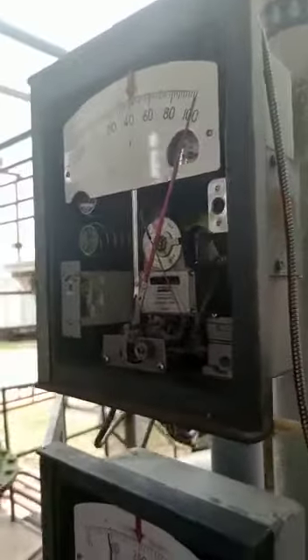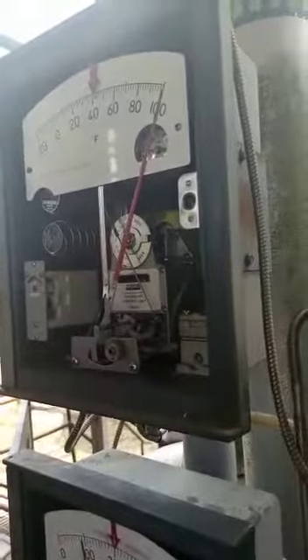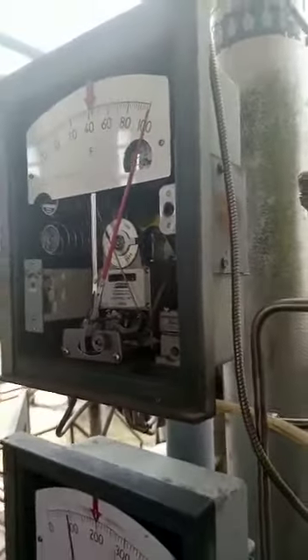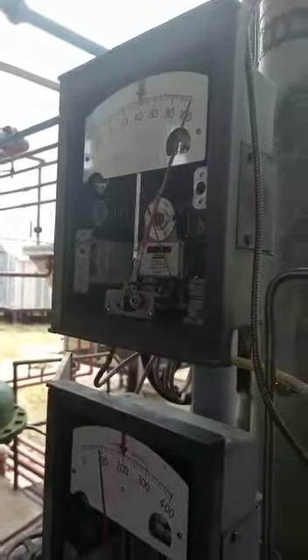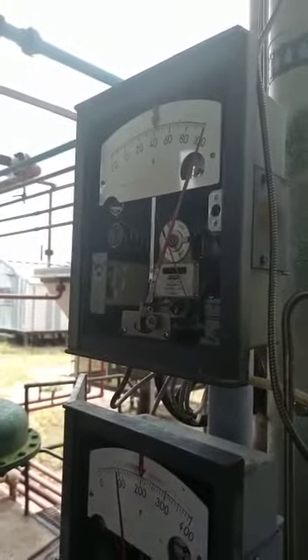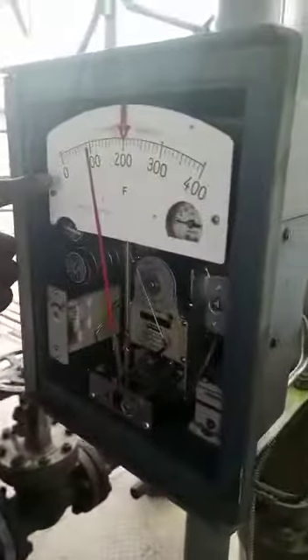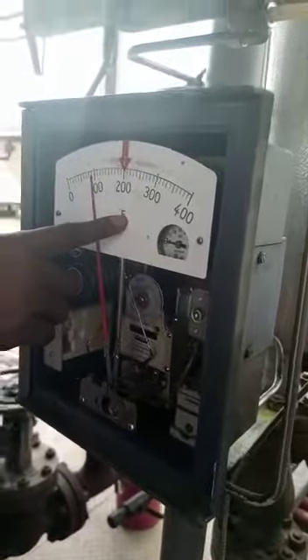We're almost there, 100 degrees Fahrenheit. Still going. Again, let me show you something. See this one, the range of this one is 0 to 400 Fahrenheit. Why is this one negative 20 to 100 Fahrenheit? The settings are different. This is 0 to 400 Fahrenheit. I've done this one, so we're using this one to show you an example. So now this is 100 and this is 100. The dry block is showing us a reading of 100 Fahrenheit, and this is 100. So it has been adjusted, it is correct now.